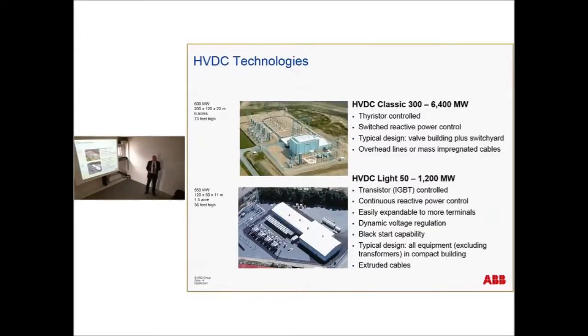The technology we're talking about is what we call HVDC Classic, for bulk transmission over long distances. It's thyristor controlled, and we control the reactive power by switching in capacitor banks and filters. This technology has been around almost 50 years now, since the thyristor control came in the 70s. Typical design is that we have a valve hall, and then we have a huge switchyard with the capacitor banks and filters for reactive power compensation of the converter itself.